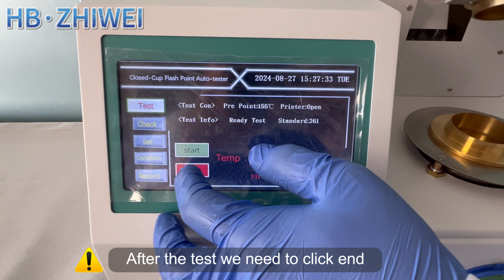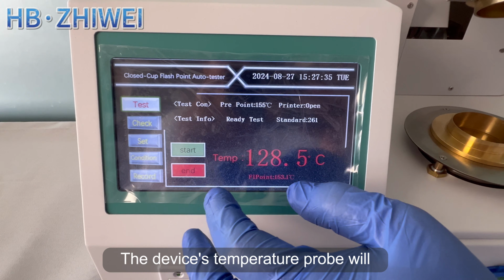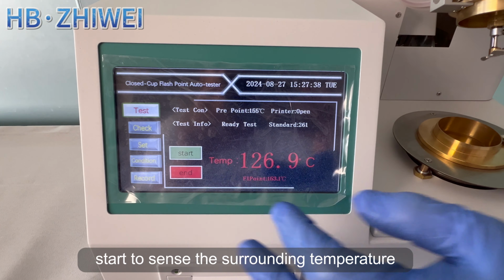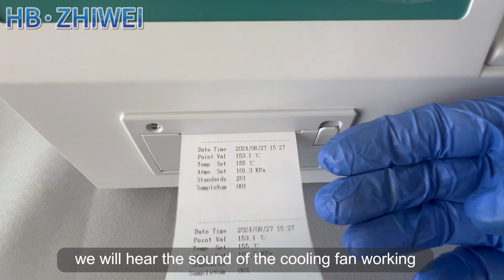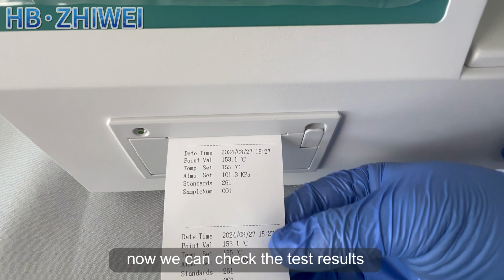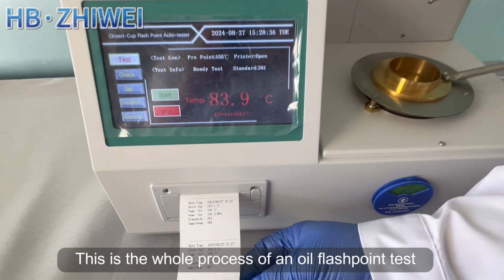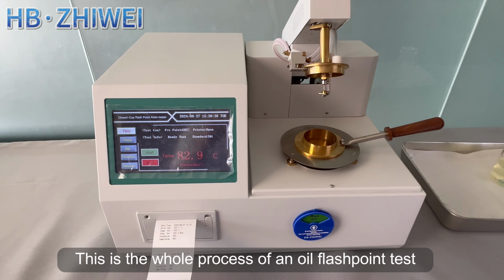After the test, we need to click End. The device's temperature probe will start to sense the surrounding temperature and turn on the internal cooling fan. At this time, we will hear the sound of the cooling fan working. Now we can check the test results. This is the whole process of an oil flashpoint test.